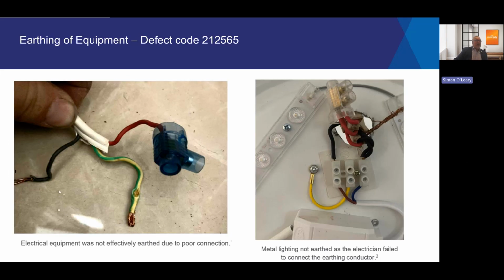Another common defect is earthing of electrical equipment. And here's just a couple of examples of equipment not earthed or where earthing hasn't been made correctly. However, this comes in lots of different arrangements. It can be from poorly secured lugs on the ends of cables, ineffective conductor size, excessive lengths of conductors as well, limiting or impeding fault loop impedance requirements. Again, the earthing of electrical equipment is extremely important to ensure that the upstream protection operates correctly and that any touch voltage on electrical equipment is kept to a minimum.